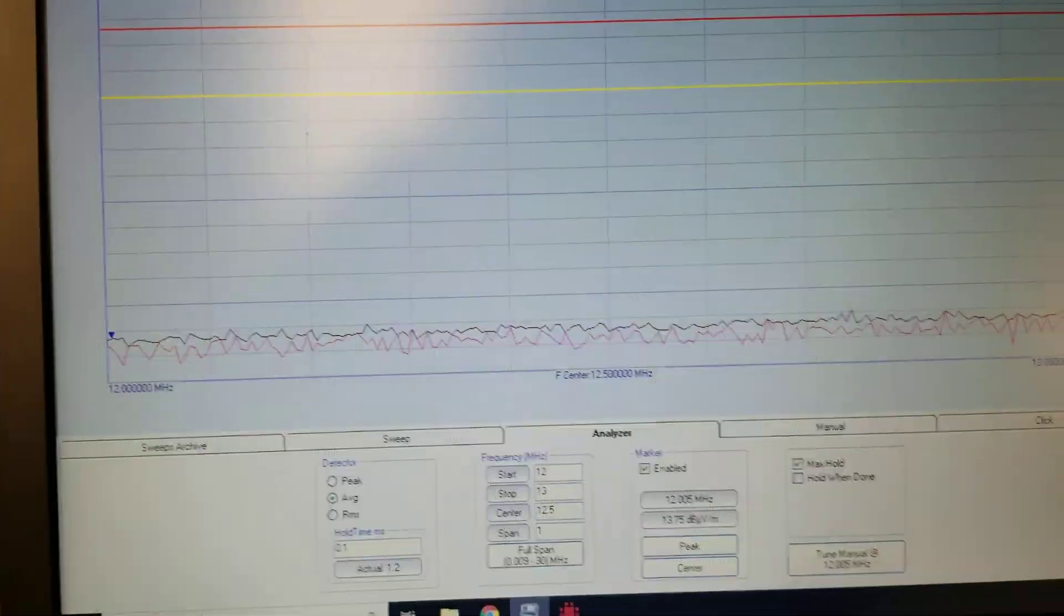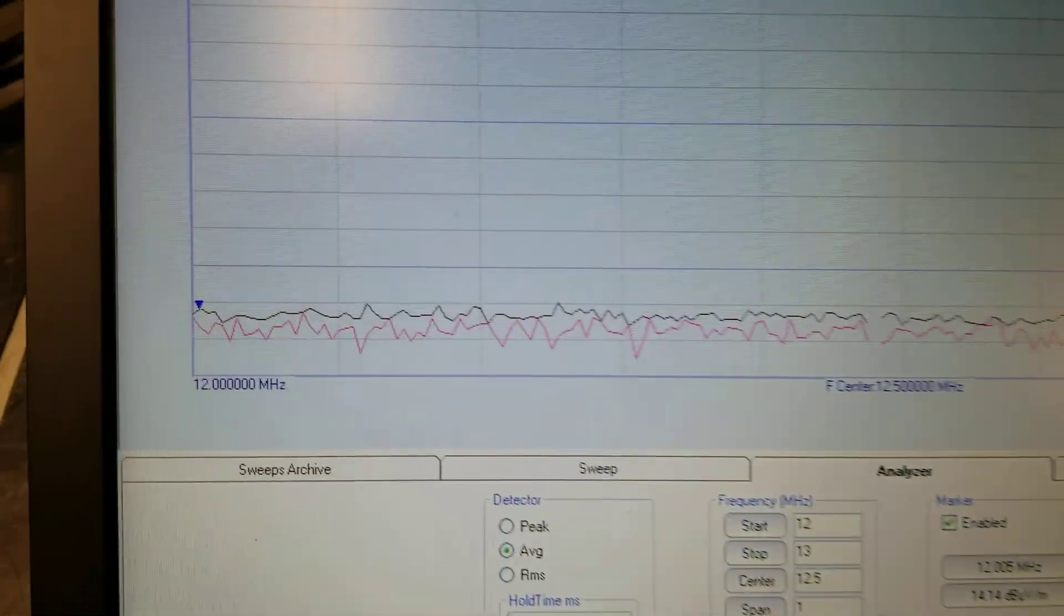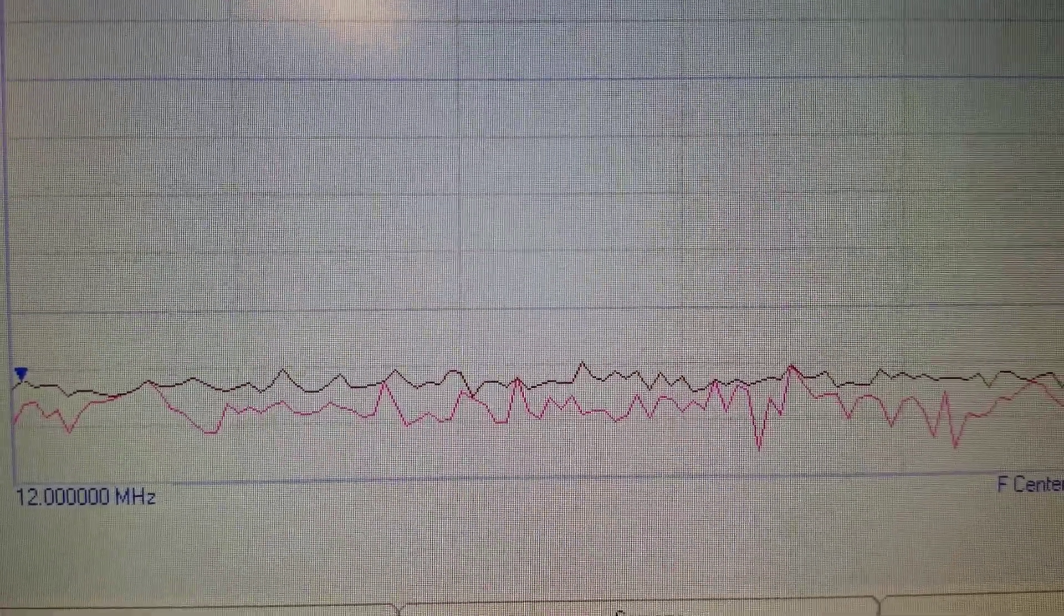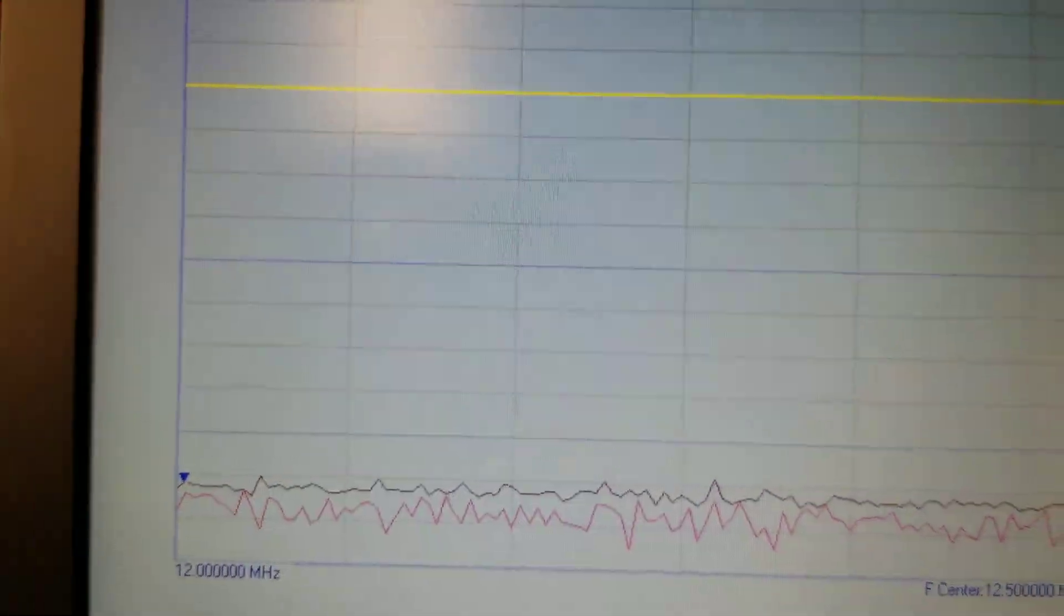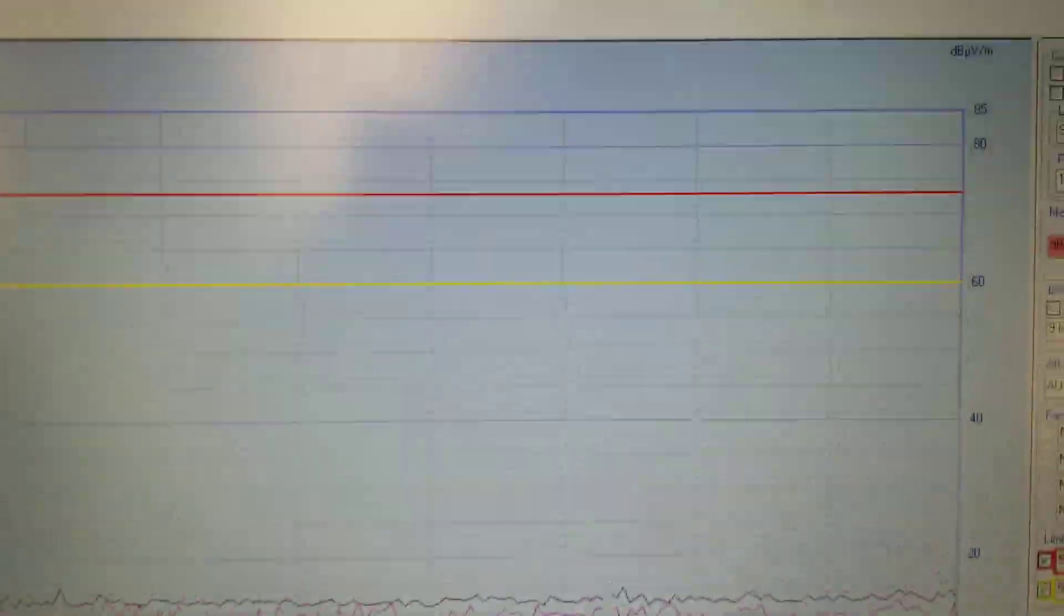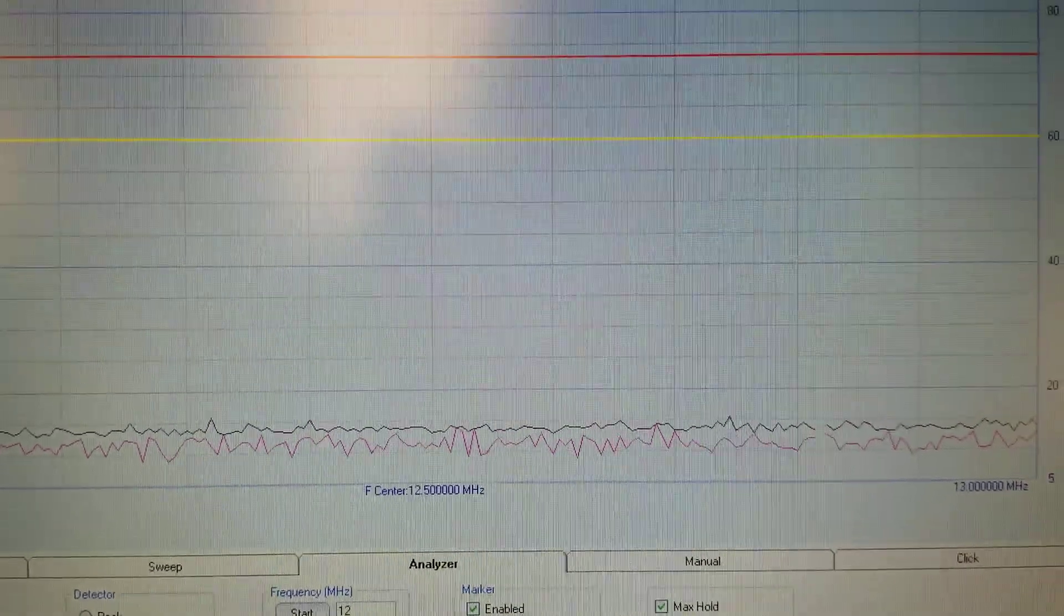On your graph you will see a pink line and a brownish line. The pink line is the constant run now time type of sweep. The brown line is the maximum hold of any voltages. The yellow line tells you you are getting close to the limit, and the red line is the limit of any spikes that you might need to see.